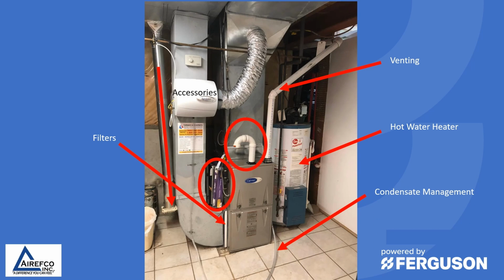The next thing we observe is the condensate. It looks like the condensate from the furnace is being directed into a floor drain. So you want to make sure that the condensate is run correctly. The last thing you want to look at are the accessories. If there's a humidifier, or if this is a propane application, or some type of accessory is being added to the furnace. So before we even open up the furnace, we have a lot of things that we need to consider to make sure the furnace is operating correctly.